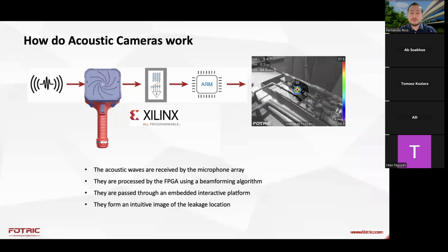For the ones that are not quite familiar with acoustic cameras yet, an acoustic camera works in a similar way that our ears work. We have a pair of them on each side of our heads, which allow us to identify whether the sound is coming from one direction or the other. Acoustic cameras do that, but not with two, but with up to 234 microphones that combine the triangulation power with a digital camera, which allows them to build a sound map on top of the digital image to locate the actual source of that ultrasound.